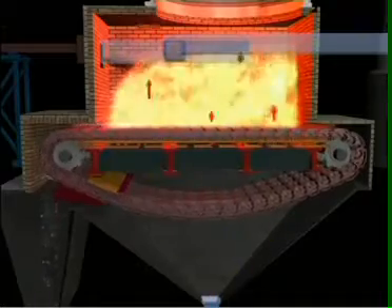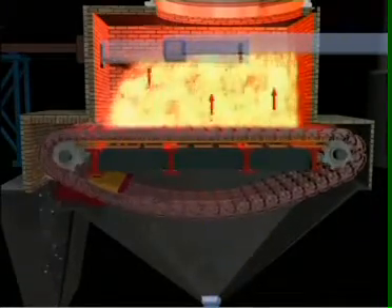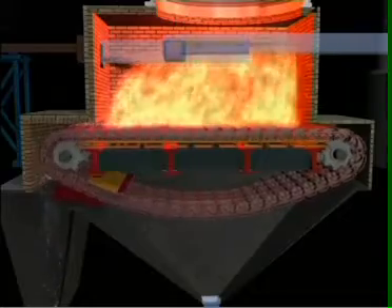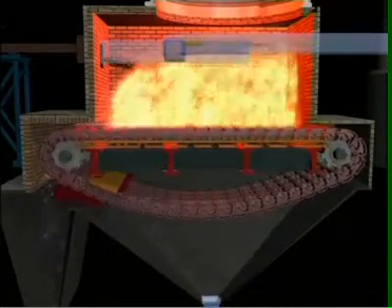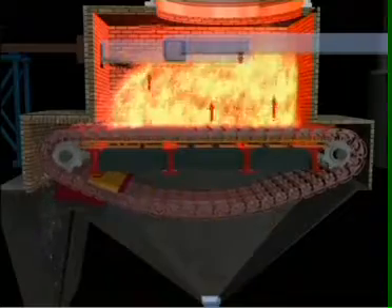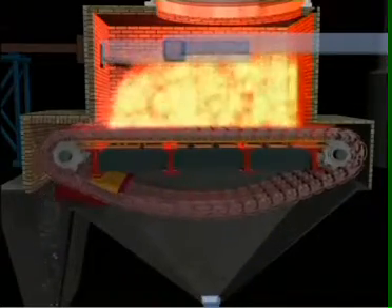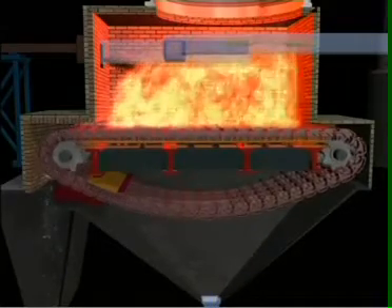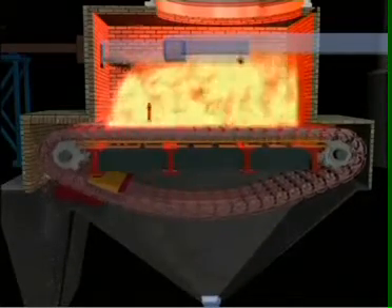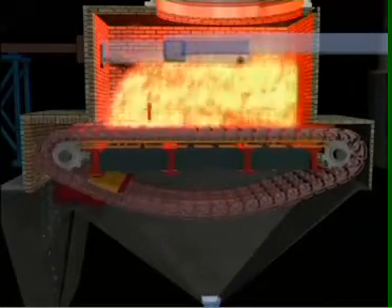The process also eliminates the cost of skilled furnace operators. An undisturbed fuel bed minimizes fly ash emission, reducing ash deposit in the heat transfer area, thus increasing heat transfer efficiency. An even bed of fuel eliminates the hot and cold zones on the grate, ensuring consistently high combustion temperatures across any given section of the fuel bed and minimizing ash clinker formation.